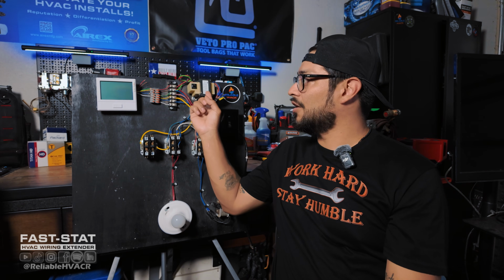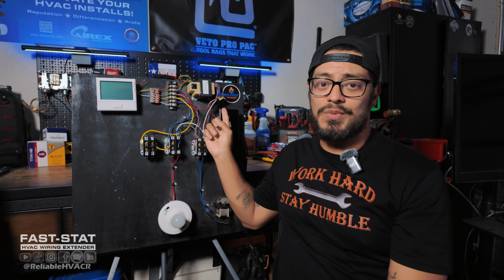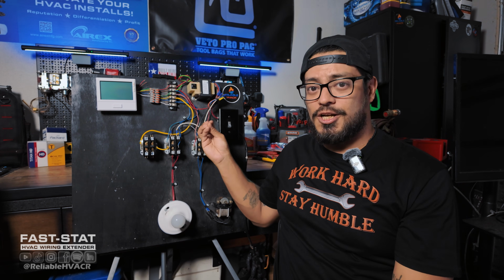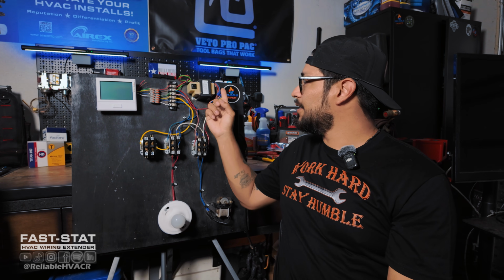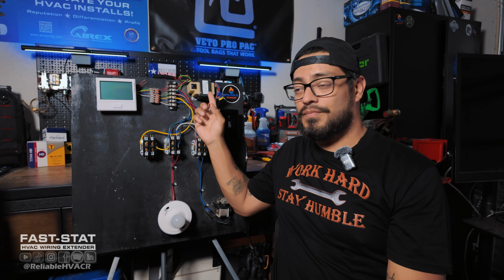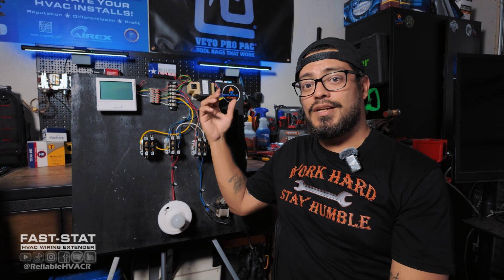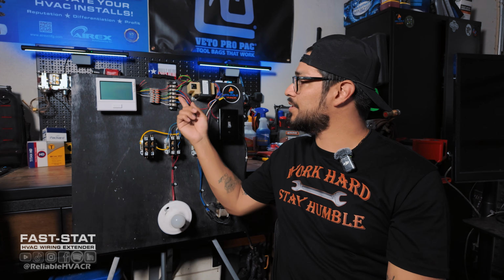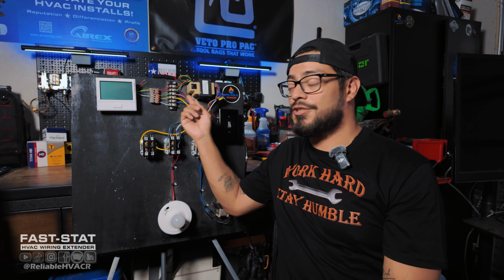So you have a transformer of some sort. That's always going to be your main or first check: make sure you have your line voltage going in, 208, 230, whatever it is, and it's going to step it down to 24 volts. And you're going to check the outlet of that and make sure that that is working.